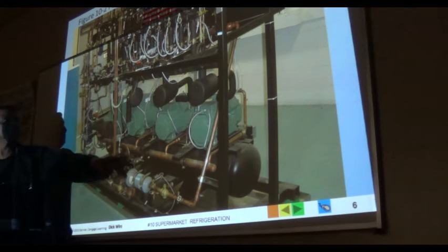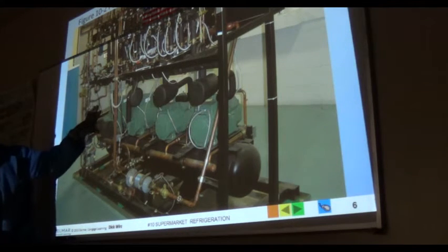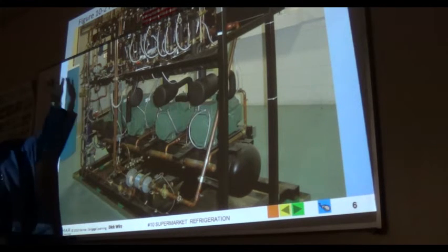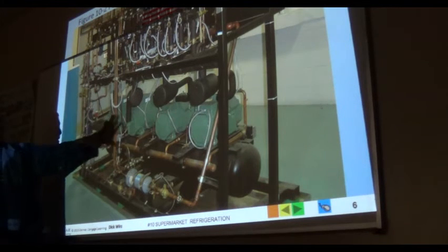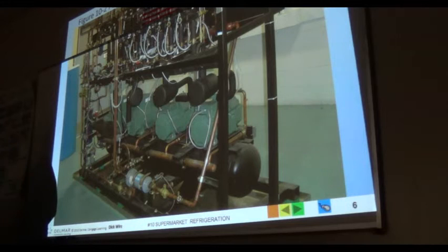Now in this system, these don't use pressure switches, guys. They use pressure transducers that go to a central controller, which will probably show up in a while. Okay, so everything is solid state. And transducers, they're a piezoelectric device that when it gets pressure, it generates a tiny voltage at different frequencies for different pressure, and it's sensed by the controller board.